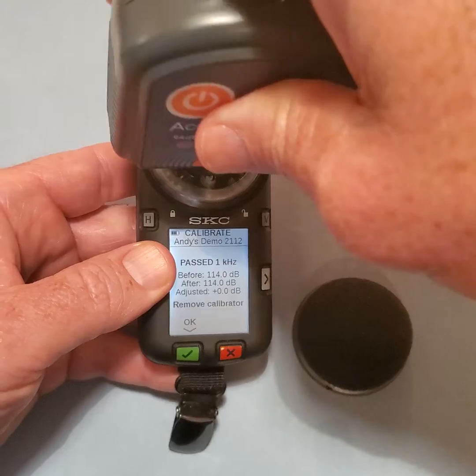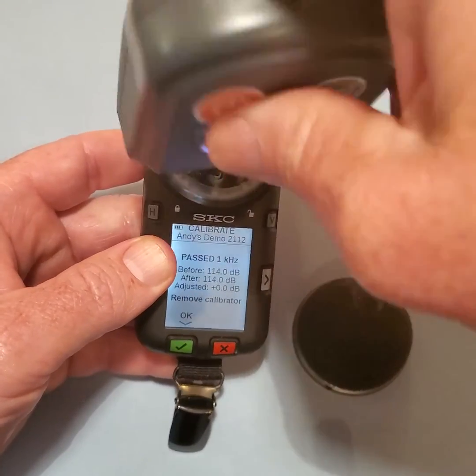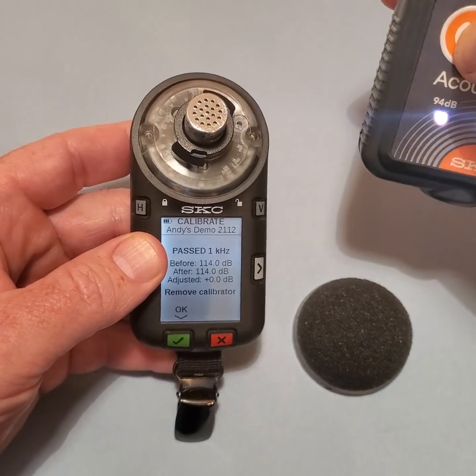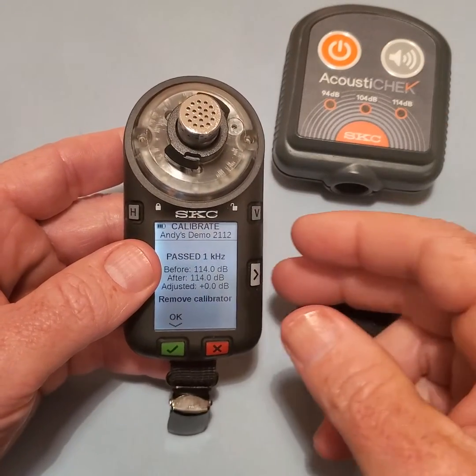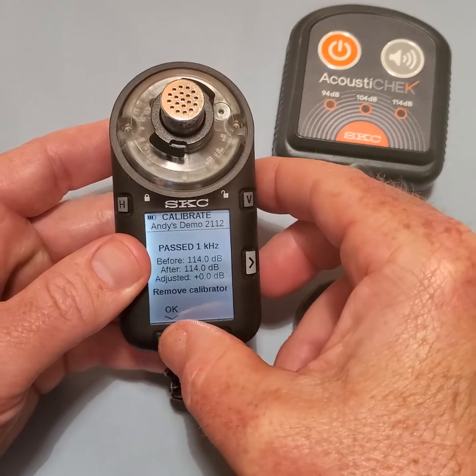Remove the AcoustiCHEK calibrator and turn it off. Select OK to accept the calibration.